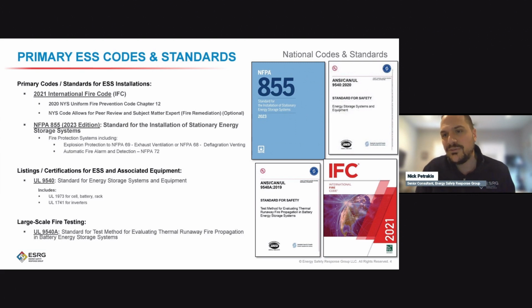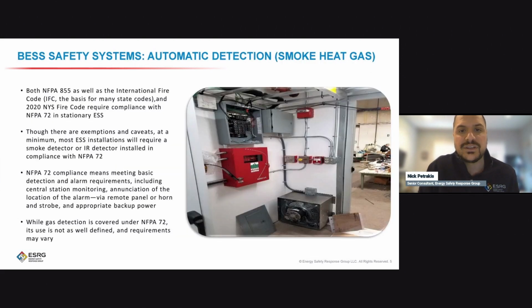If we understand how it fails, we can understand how to design these fire protection systems—critical ones like explosion protection, to make sure it does not deflagrate, and also proper spacings and separations to ensure that if there's a fire in one system, it doesn't jump to another and involve a larger portion of the facility.